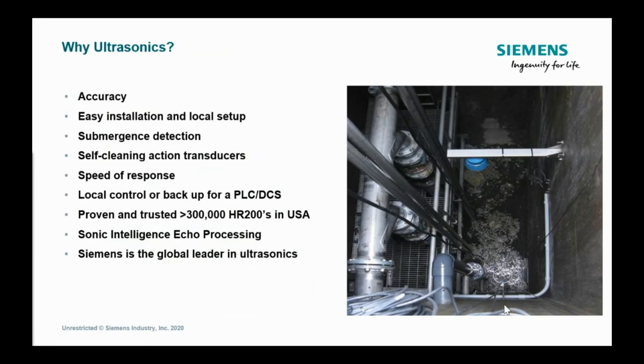The thing about ultrasonic is it's not a technology thing, it's a physics thing. The long wavelengths of the acoustical waves, so it's going to be in the kilohertz range, actually will give you a more accurate measurement if that's your primary driver over the really short wavelength of something that's in the gigahertz range, such as a radar. Okay, and so yeah, if you take the best radar and the worst ultrasonic, you're going to flip that curve. But generally speaking, ultrasonic is a more accurate product to use. That's why it's still around.